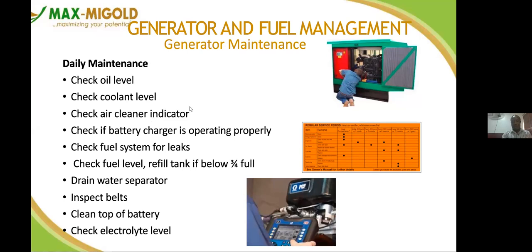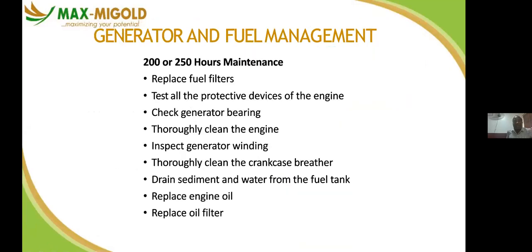We also have what we do at every 200 or 250 hours maintenance. This is where most of us belong, what the majority of us are aware of. When you ask anybody when do you carry out generator maintenance, they will tell you every 200 or 250 hours. So you are right. What you should be paying attention to is to ensure that the fuel filter is replaced at every 250 hours.